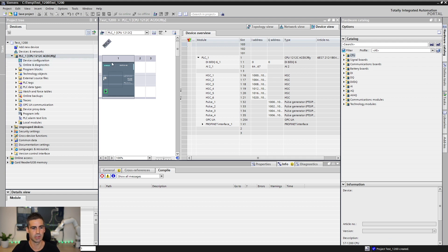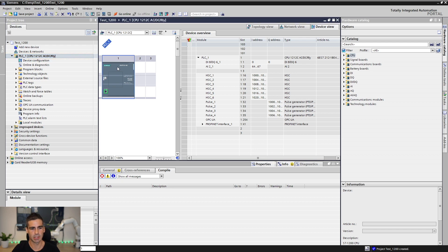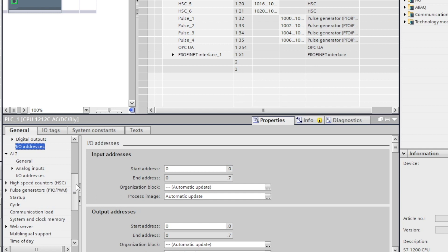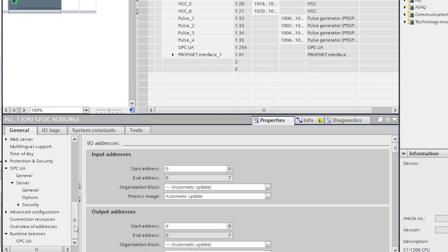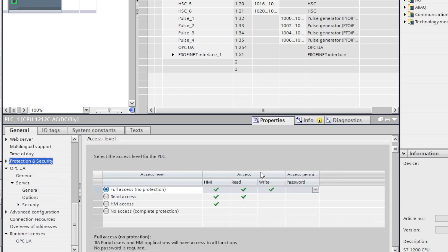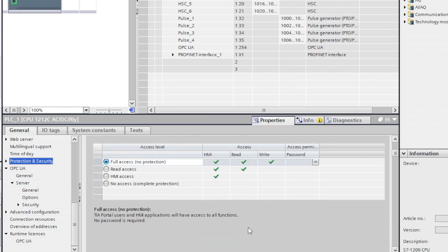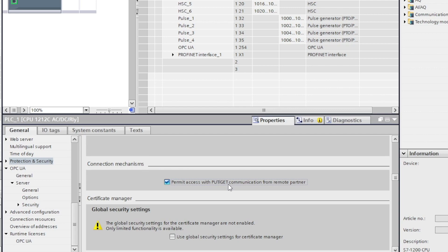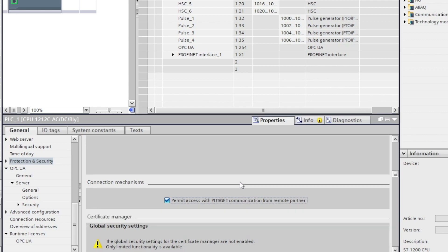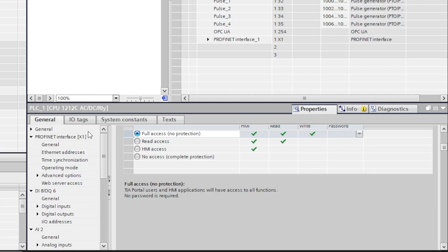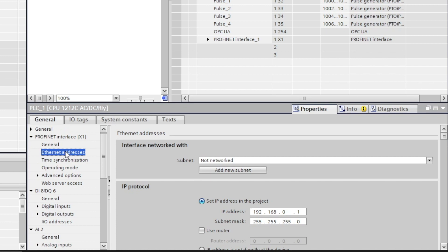We just go here to the PLC and we are gonna double click in the CPU and we are gonna start doing the protection or security settings. We are gonna make sure that we have allowed full access to the PLC - that is because we want Simumatic to be able to communicate with it. Because we are gonna be using this S7 protocol, we need to check this box here, allow PUT and GET communication. Once we do that, now we can start defining the IP address of our PLC. Let's come here, we are gonna set the IP address of the PLC.